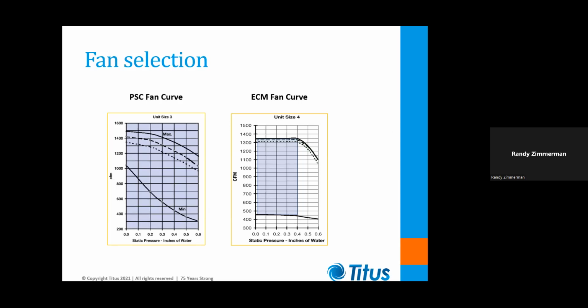Now, if you look at these two fan curves, you're going to see a PSC fan curve looks very different from an ECM fan curve. The PSC fan curve, we've got a maximum curve, and then we've got a 1-row curve and a 2-row coil curve. Then we've got a minimum curve. And that minimum curve is the 600 RPM curve for the PSC motor. You never want to go below that minimum curve because below 600 RPM, PSC motors with their sleeve bearings don't properly lubricate, and you rapidly get rapid wear on your bearings and overheated fan motors. And so you want to stay away from that curve.